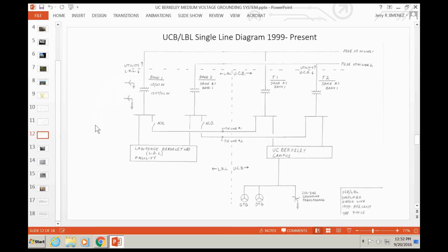The generators, what voltage level? Those are 12.47 kV. Do they have unit transformers, or are they directly connected onto the system as you've shown in the single line here? Those are directly connected. So the distribution is 12 kV, so they just feed right into the distribution system. Well, that's very interesting. We've got a couple of generators on my campus, and we do have unit transformers for them, even though they're basically a 1-to-1 ratio. And we did that to limit fault current and to provide some voltage stability as well. We do have some current limiting reactors that I didn't show, but they'd be here on the diagram. They help a little bit with lowering the amount of fault current that comes from the cogen plant when we have a fault. Okay, interesting.